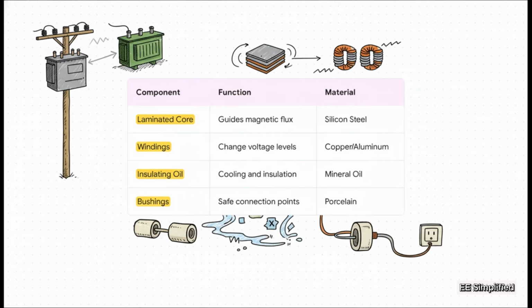Inside that box, you've got a steel core that guides the magnetic field and copper windings that do the actual magic of turning 11,000 volts into 230. The whole thing sits in a bath of mineral oil to keep it cool, and those porcelain knobs you see on the outside are called bushings, just safe insulated connection points for the wires.